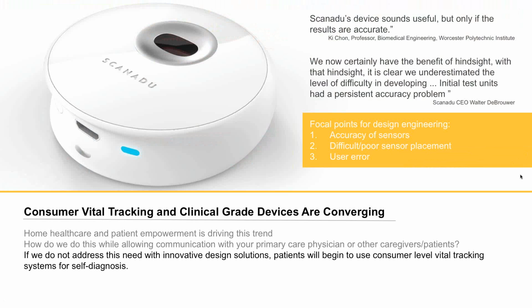It was an issue. So again, going back to why this is important to us as engineers and designers, and why we have to think about it: here are three big focal points for addressing these kinds of issues. One of them is the accuracy of the sensors. Again, we talked about that, and Mark will talk about this a little bit too, but sensors obviously get more and more expensive as they get more accurate, and time has to go by before that changes. The second is the difficulty of sensor placement, or poor sensor placement. This speaks to where we put the sensor on the device, but also how the device enables the user to put the sensor in contact with their body. That's a huge, huge issue. And of course, user error too. Does the user understand how to use it so the sensor is working?